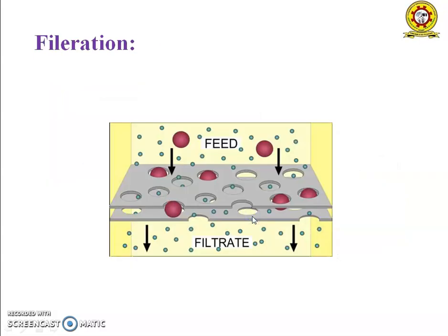And the next one is filtration. In this method, water is allowed to pass through the gravity or pressure filters. So these are the gravity or the pressure filters. By increasing the fineness of the filtration element, maximum suspended impurities are removed. The suspended matter adheres to the filter material and clean water drains from the bottom. It is necessary to clean the dirt collected in the voids and filter material periodically by backwashing the filter material, which can be recycled.